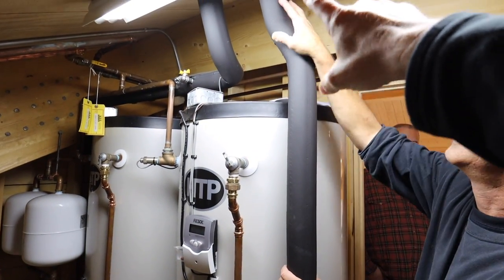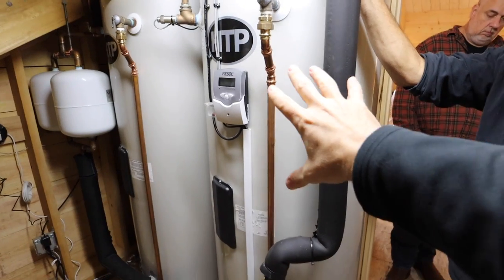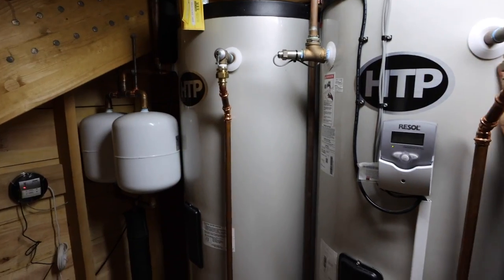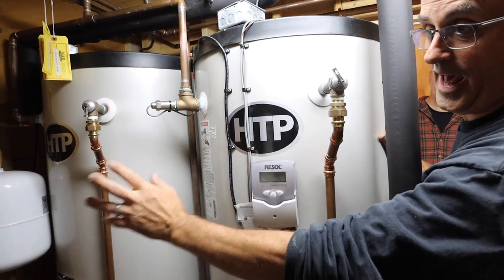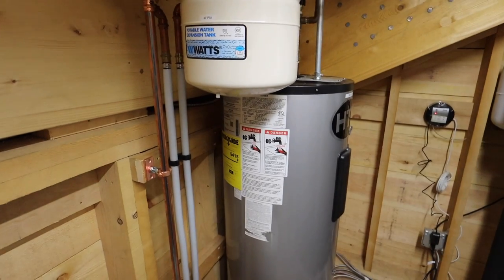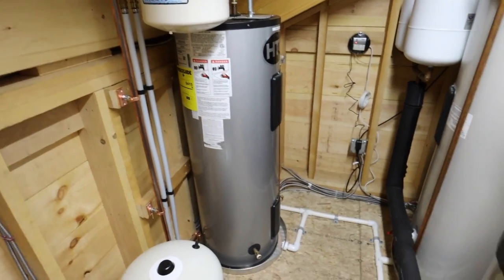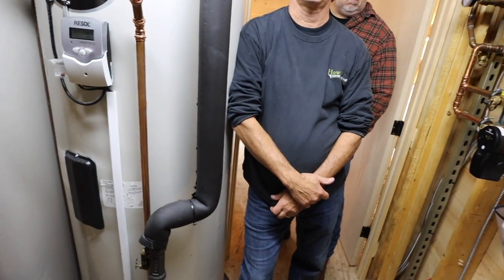This is the circulator for those. You've got glycol running in here. We've got a big panel of solar collectors on the roof — it comes down here, and these are storage tanks with no additional heating going on in them. The glycol runs almost like a hot water heater in reverse. This is actually domestic potable water — it comes from the well system, comes through here, is heated, and then goes into the domestic hot water tank as supplemental hot water. There's an electric element there in case we need a little more heat. You've got about 240 gallons here collecting and hanging out, then it can send over to a 40-gallon tank. All HTP products — all stainless tanks.